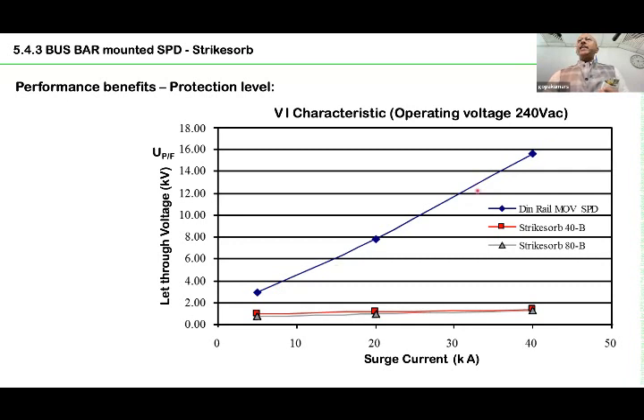Whereas this blue one is a DIN rail mounted SPD with a 250 mm wire length, not a big wire, just 250 mm. For example, at a 10 kiloampere surge current, the SPD with wire has clamped the voltage to about 4 kV, whereas the bus bar mounted one is still 1.2. At a 20 kiloampere surge, the actual voltage going into your equipment is about 8 kV, whereas the bus bar mounted one is still 1.2 kV. So basically, once you connect the SPD, you have to use the shortest wire. If your equipment is more and more sensitive, then a DIN rail mounted SPD sometimes may not be efficient, and you have to go for this kind of SPD.